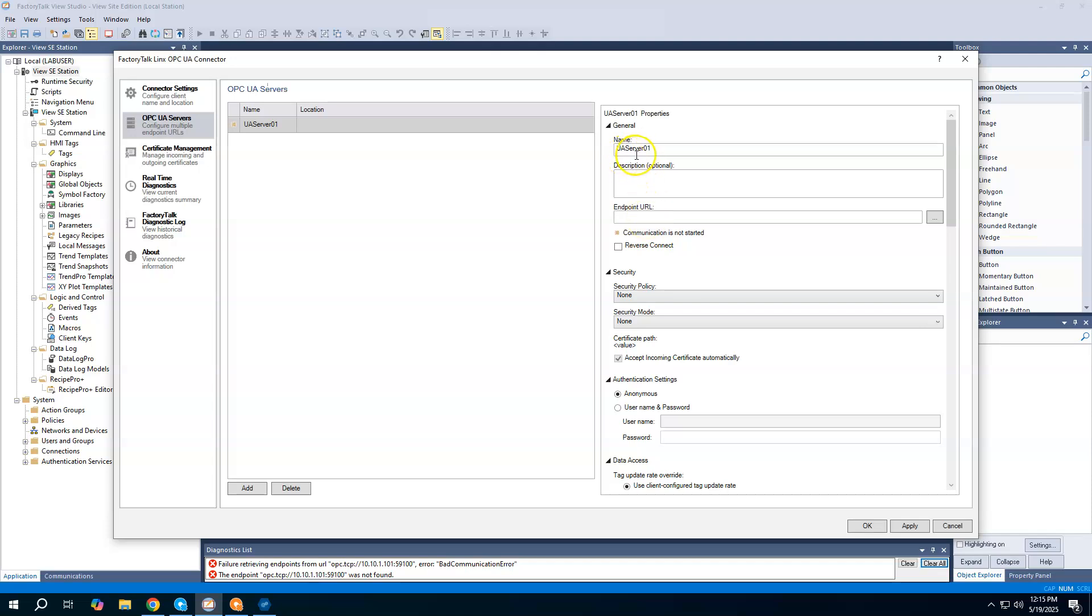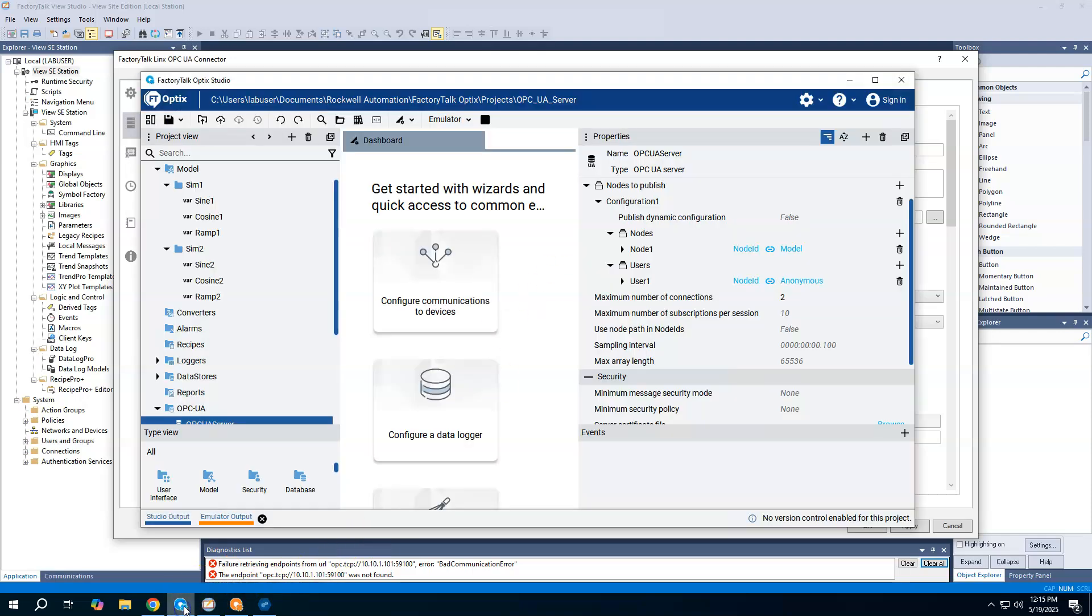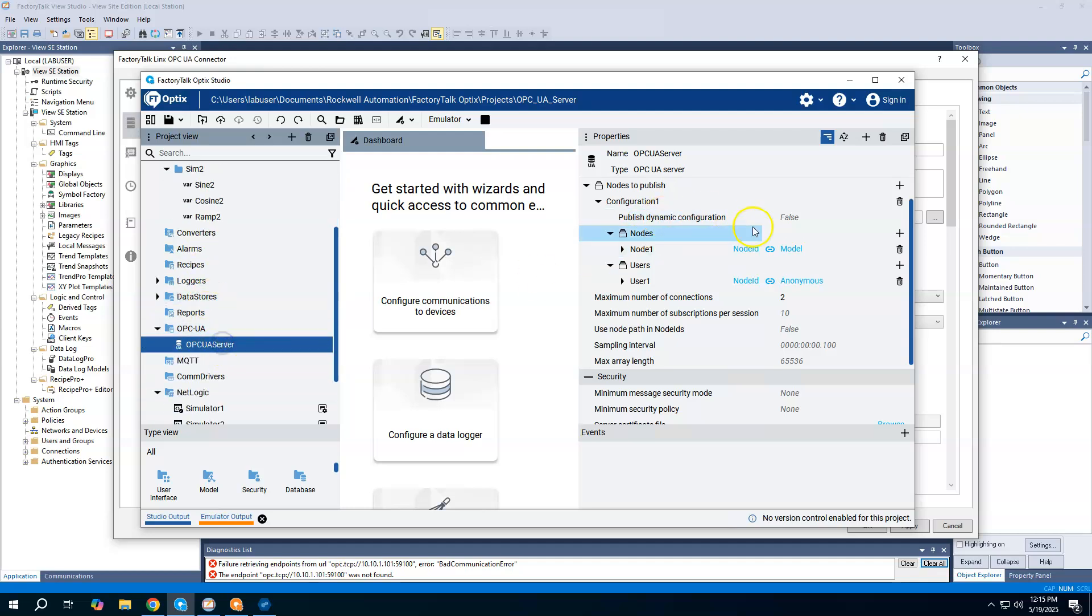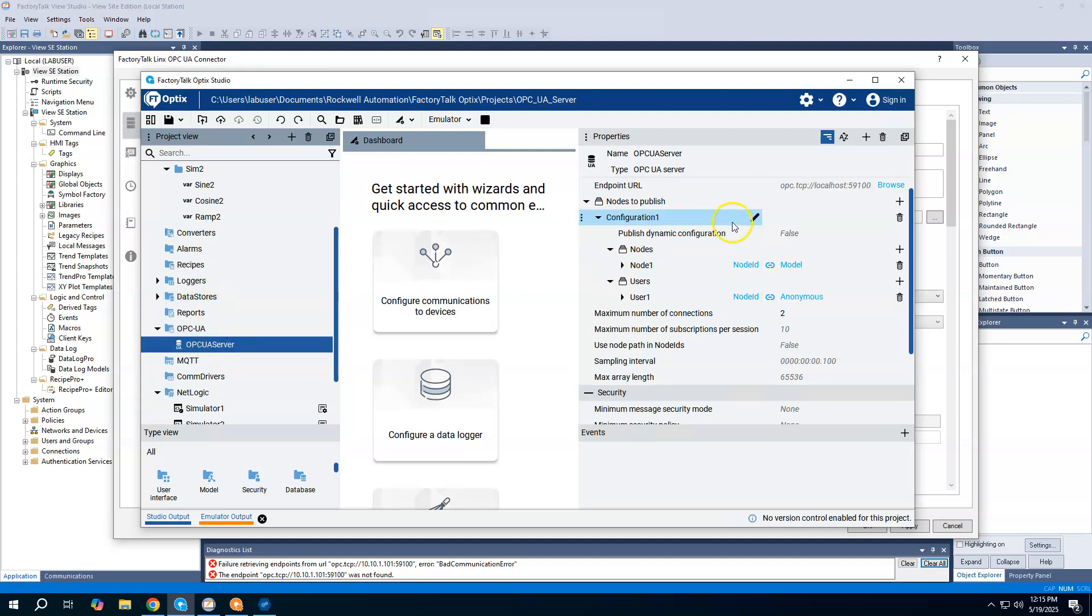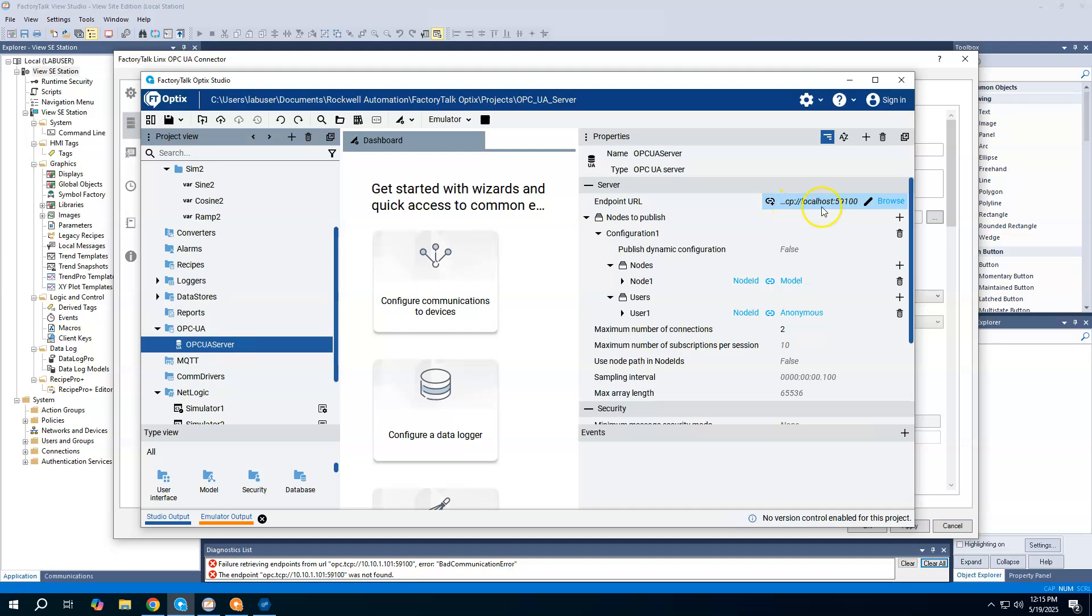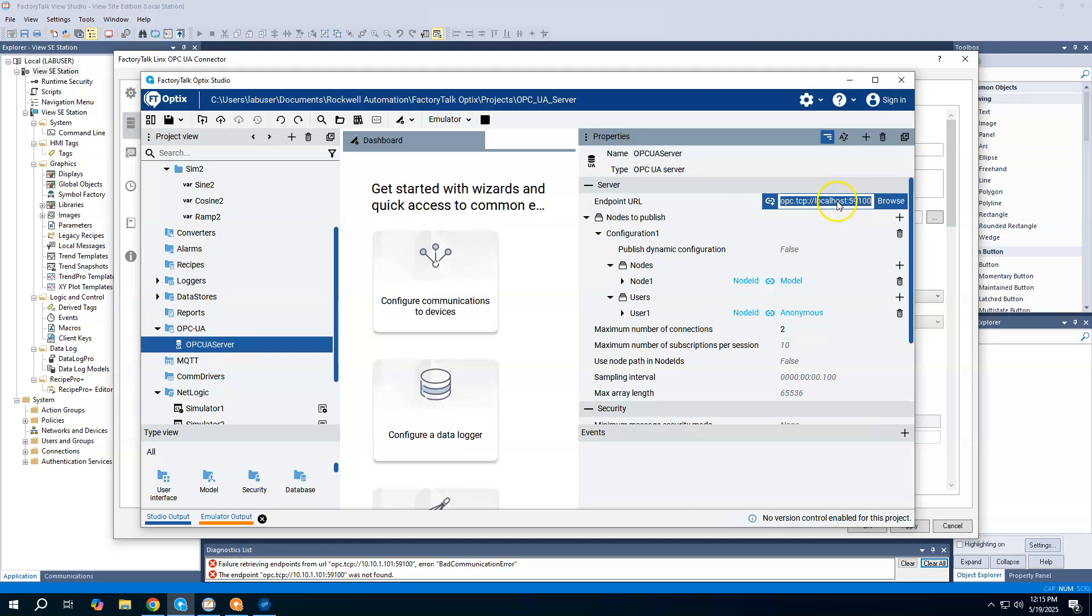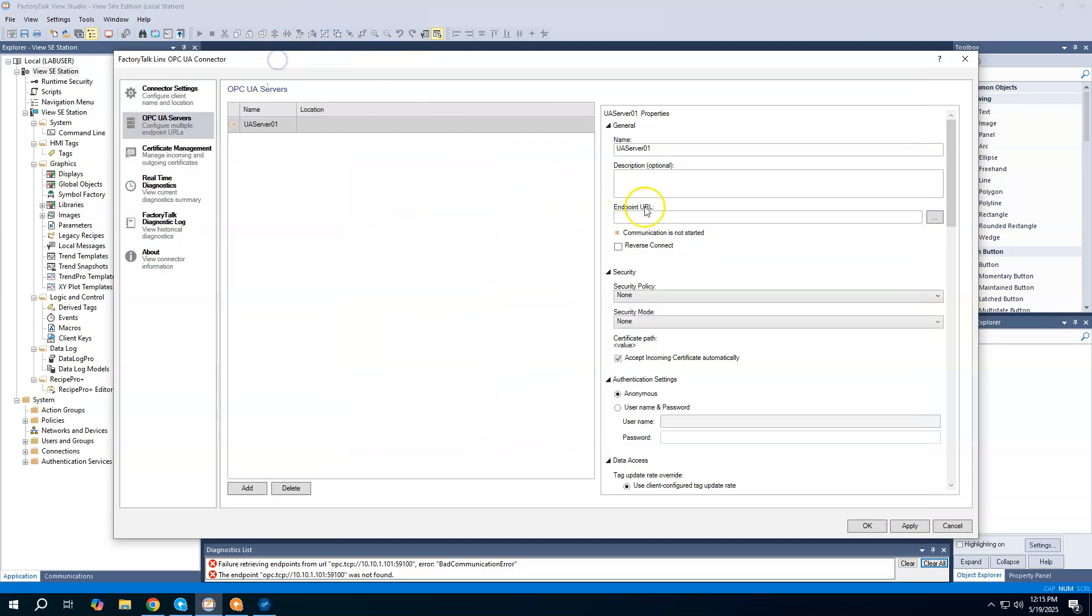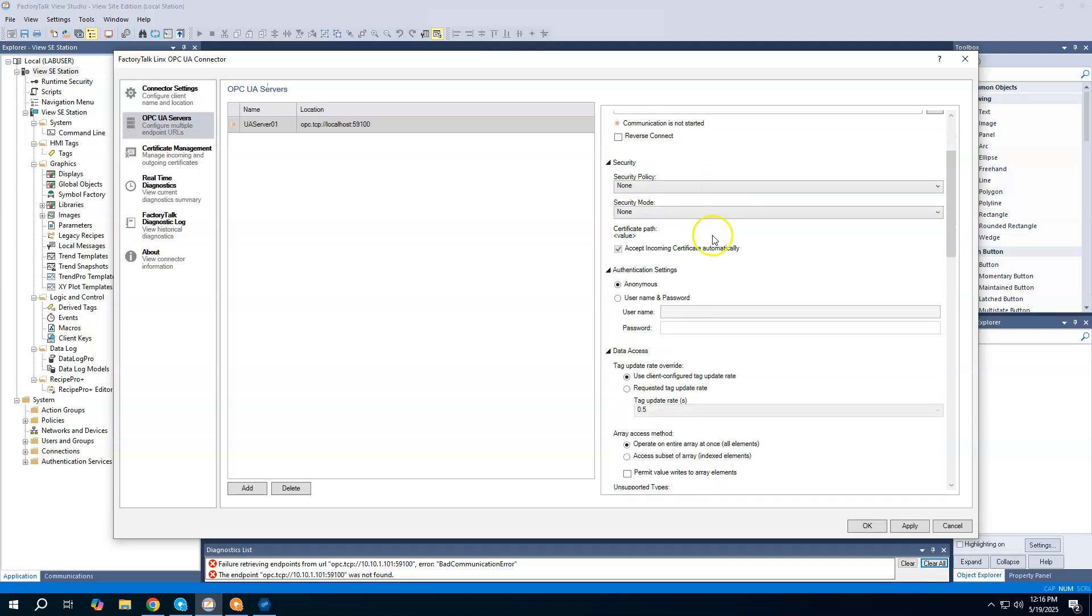Next, we come to the OPC UA servers tab, and now this is where we will define our server information. The server name is UaServer01. We can give it a description. You can change the name as well. I could call it Optix or whatever it's coming from. I'm going to leave it default. Then the next piece is the endpoint URL. That is going to be our endpoint URL right here. I could type it in, or if I wanted to, I can come back here to Optix and copy it. We'll come to our endpoint URL and paste it.